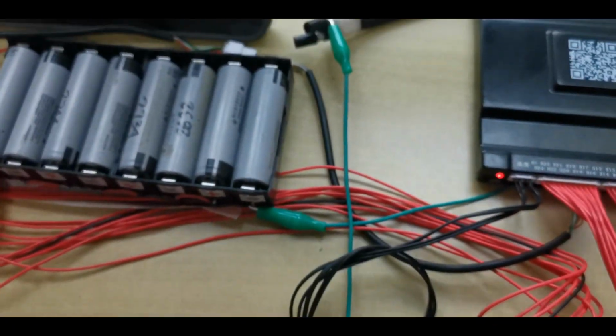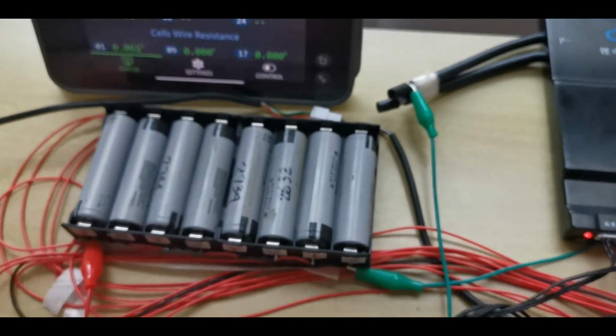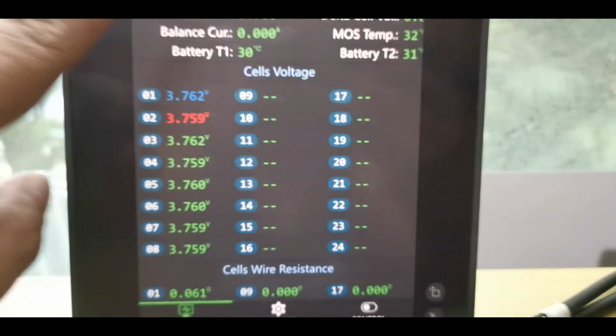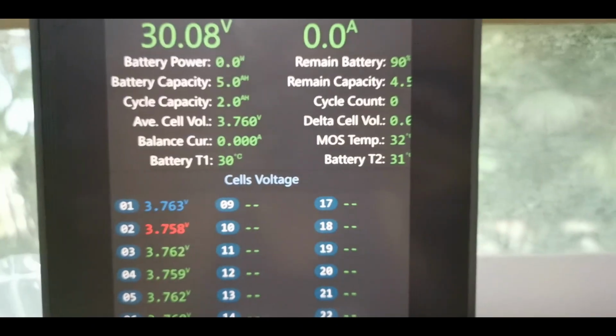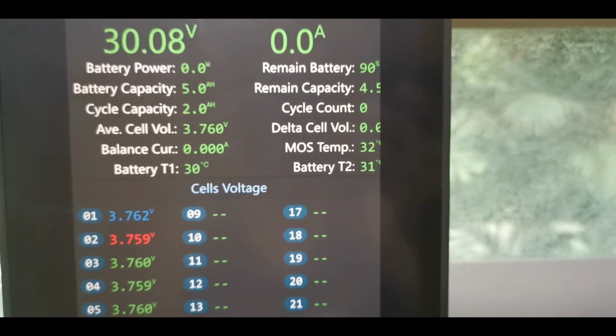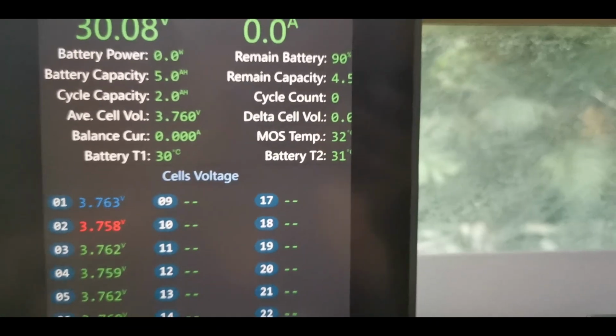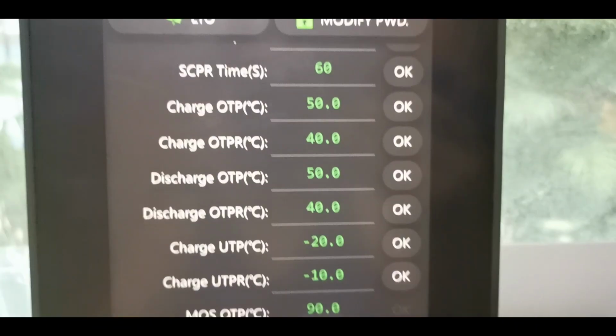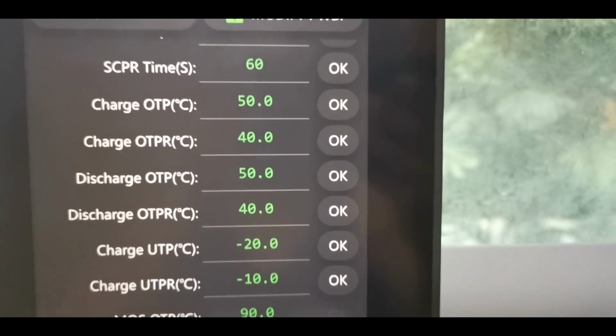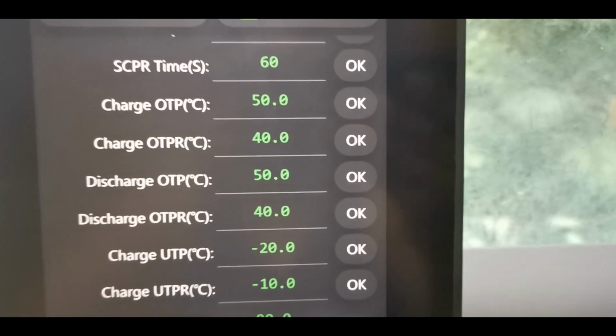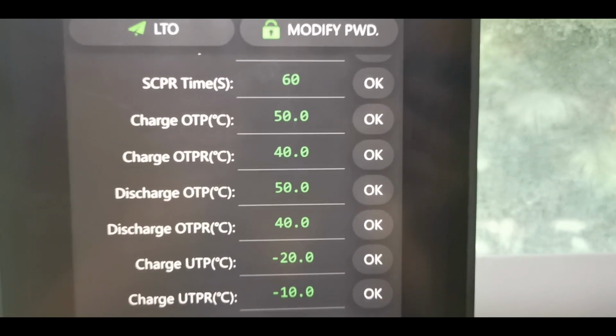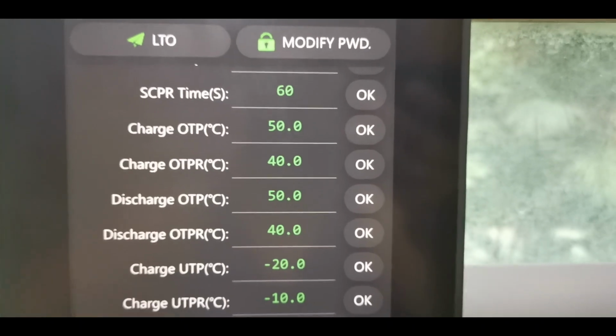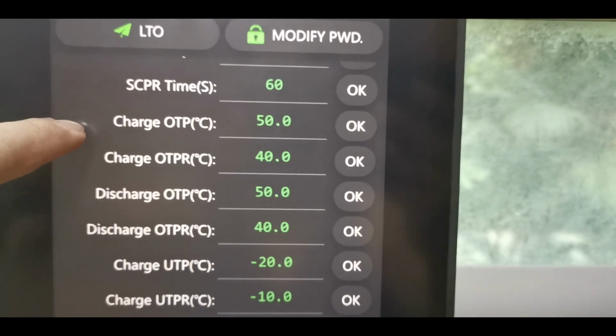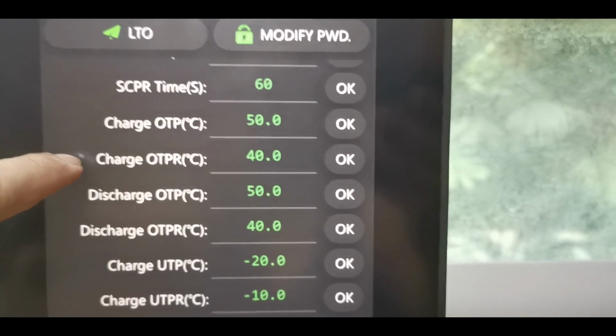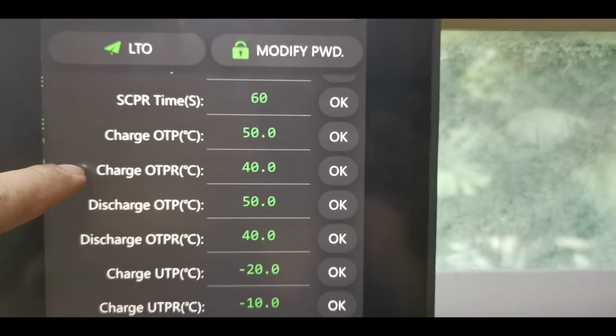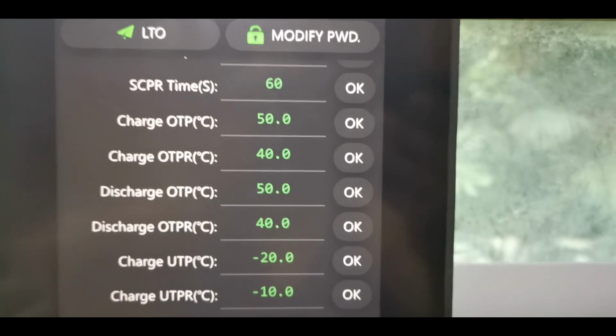We can test it now for the over-temperature protection. Currently our temperatures T1 and T2 are 30 and 31 respectively. If we check from the settings, the charge over-temperature protection is set to 50, and it will release when it drops to 40 degrees. Alright, let's test that out.